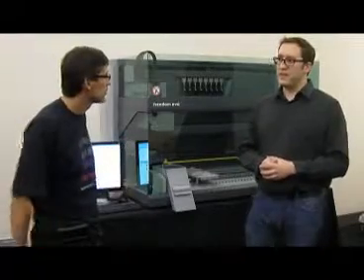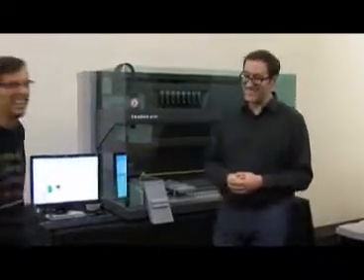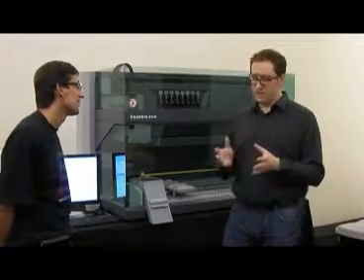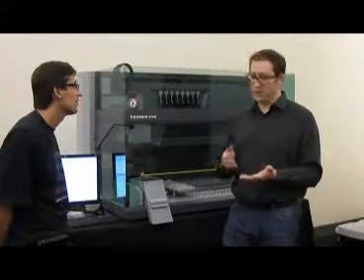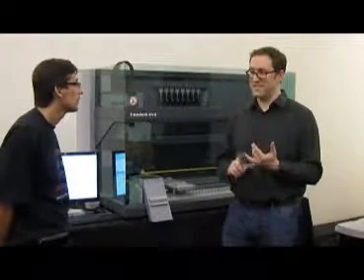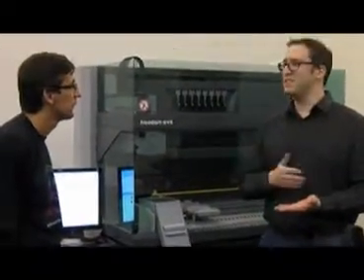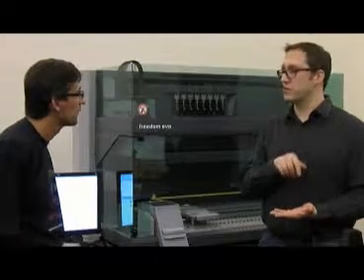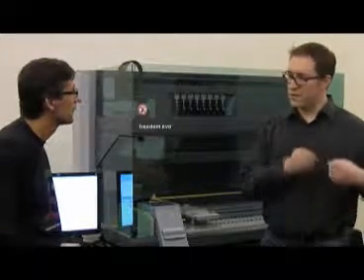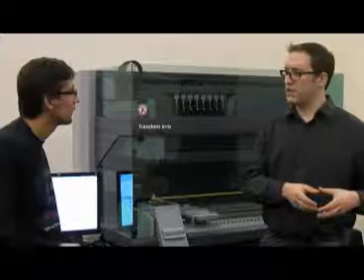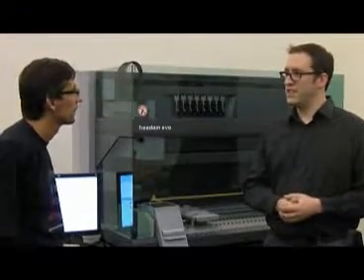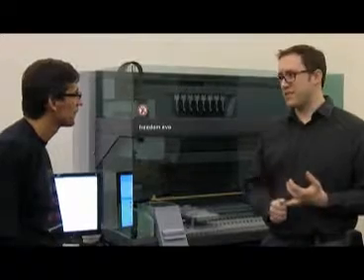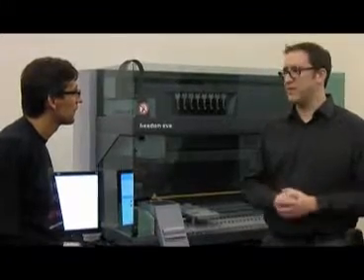We do. We're actually very excited to be partnering with Hewlett-Packard to be bringing you the HP D300, which is designed for titrations. And what it can do is it can go from 13 picoliters to 5 microliters. And it allows you to replace the dilution in a serial dilution by dispensing your samples directly into the wells. So you can put 13 picoliters directly into whatever your target well is, instead of trying to dilute down to those volumes. And it speeds up the process and allows a lot of flexibility in the way you do the plate maps and all that kind of thing.